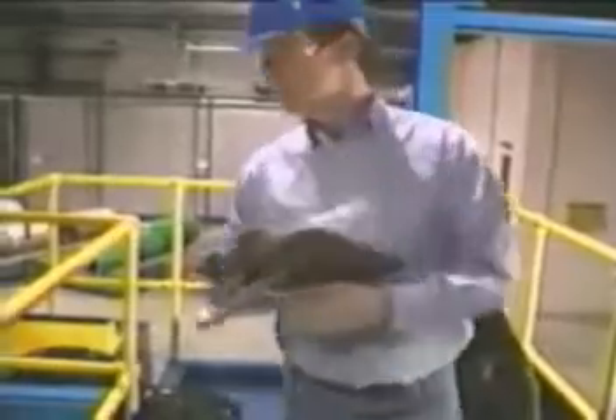Your company may require you to follow a checklist of required steps to reactivate the machinery so that no one is exposed to danger during startup. Be sure to notify affected employees that you have removed locks and tags and the equipment is ready for use. If you are not finished service or maintenance on a system and a shift change occurs, always wait for the employee who is replacing you to attach his or her lock before you take yours off. Don't ever leave your lock on once your shift is over.